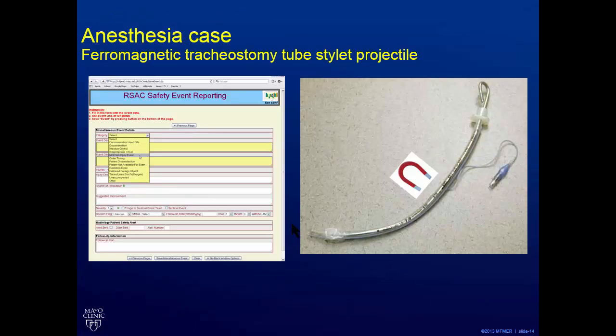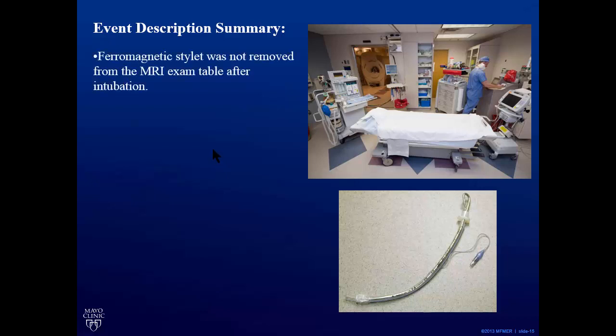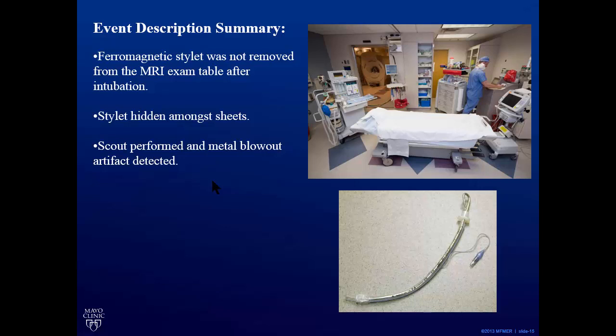Let's start with something real basic: a projectile incident that we had. At our shop at Mayo Clinic, we have an internal event reporting system that we do online, and that's been very valuable for knowing what's going on in the department. What happened here: a ferromagnetic stylet was not removed from an MR exam table after an intubation. It was hidden amongst the sheets, the scout was performed, and the tech saw some metallic blowout.